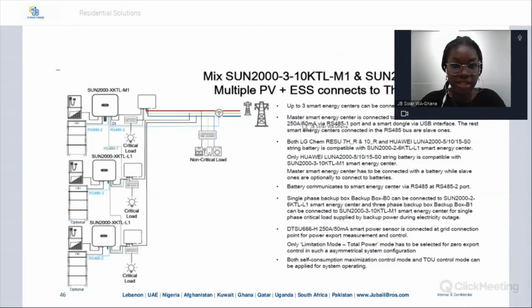So this is also multiple inverters connected to three-phase grid. Here, the connection between them is the RS485. Between each inverter is the RS485. They're all connected to a backup box, the backup box, the critical load. For inverters connected in such a way, one inverter is the master inverter, and all of them are connected to it in series. So this is connected to this is connected to this, and this, which is the master, is connected to the power sensor, and it's connected to the dongle. And as I mentioned earlier, you can connect multiple inverters to the dongle. The maximum you can connect in this range, if you have energy storage, is 3 inverters. So if you have batteries, the maximum you can connect is 3 inverters to each dongle.